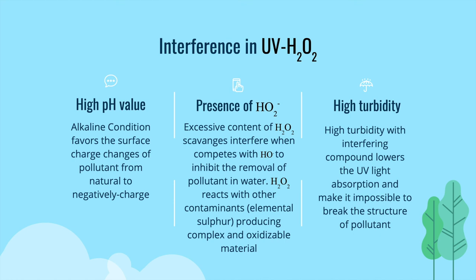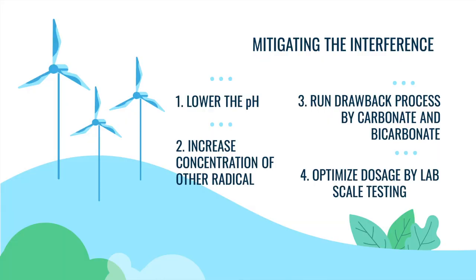All of these interferences can be mitigated by several methods. The first is by lowering the pH value of the water to reduce the alkaline condition. The second is by increasing the concentration of other radicals slightly to avoid interruption during the process. The third is to counter the presence of hydroperoxyl radicals as inhibitors by using carbonate and bicarbonate, which act as scavengers to the hydroperoxyl radicals in the natural system. The last method is optimization of dosage by lab-scale testing from each water source to ascertain the ideal dose of hydrogen peroxide, since excessive dosing will cause major interference by producing complex and oxidizable materials.